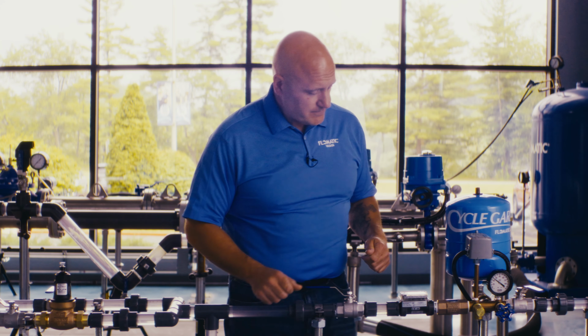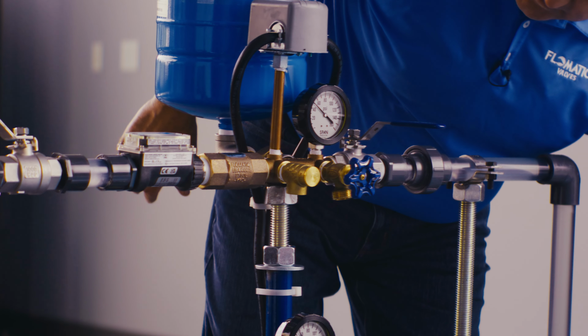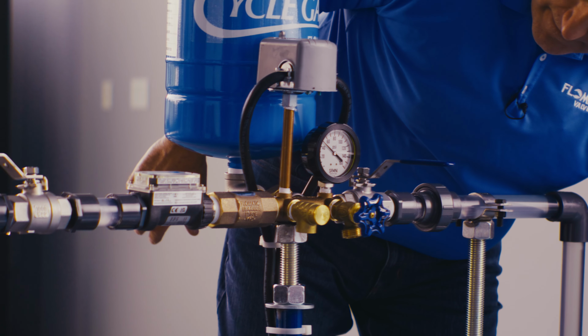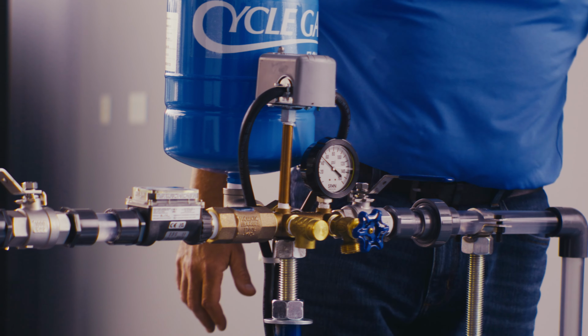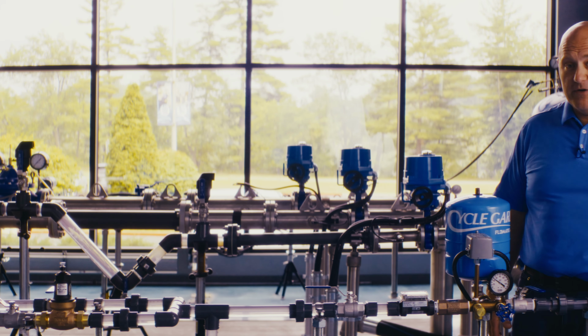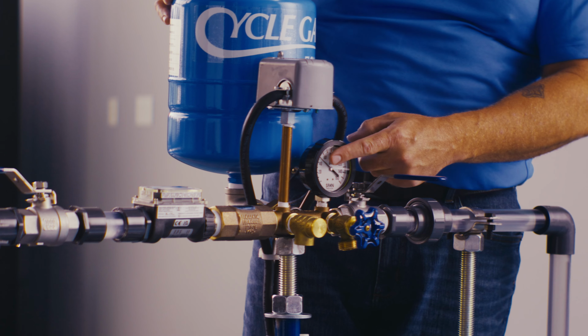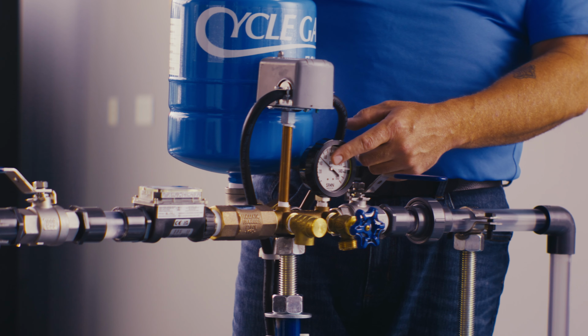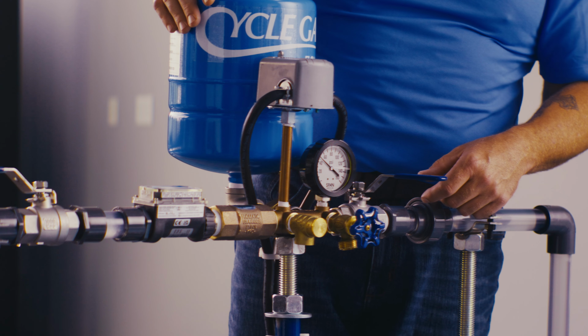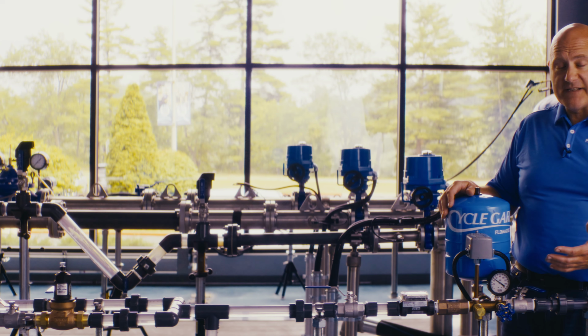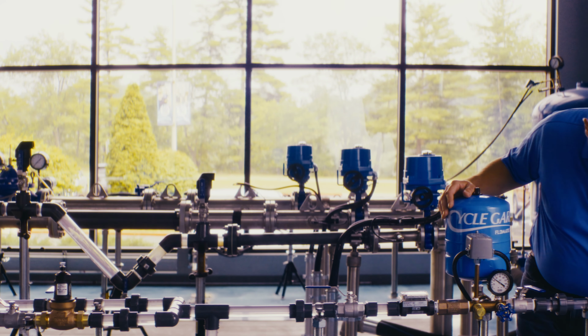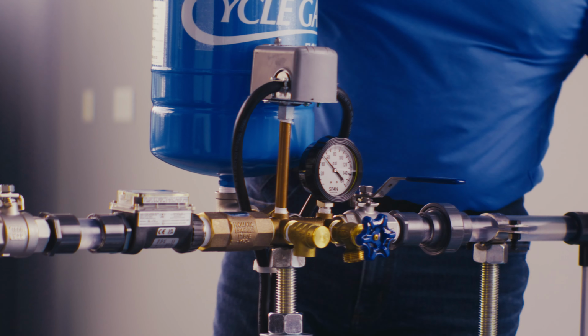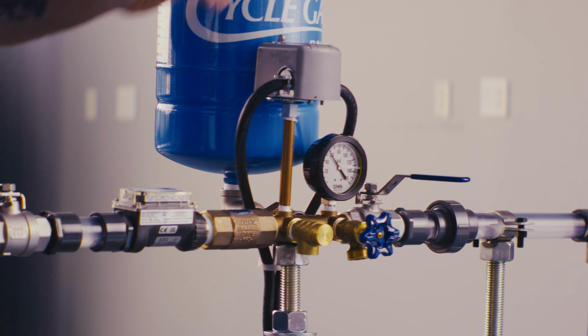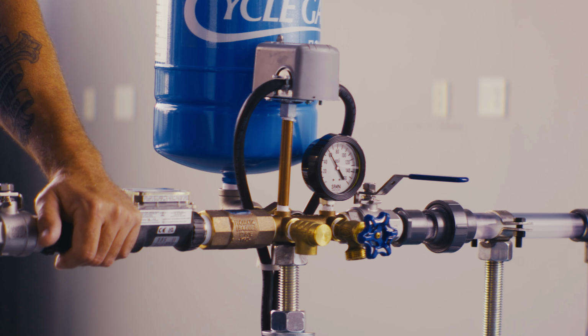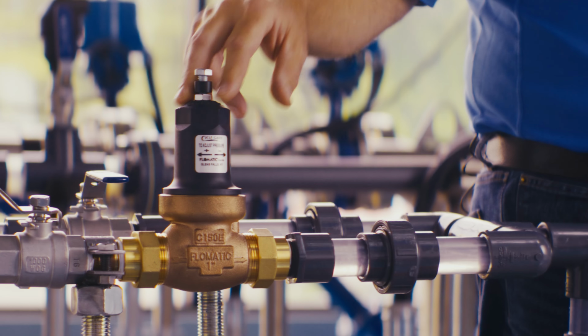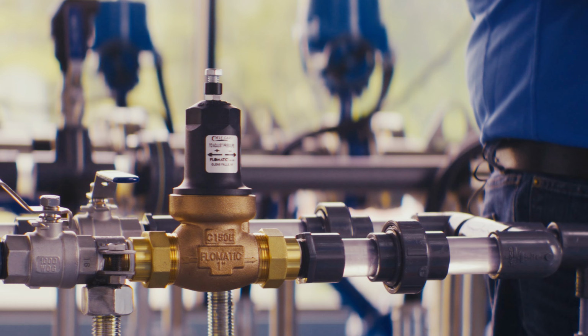to satisfy the demands of the home. So you'll notice if I allow more flow through this valve, meaning maybe a sprinkler system went on or multiple points of use in the home, you'll notice the pressure drops some on our switch. Again, that's a function of the fall off of the valve. Notice the pump's been running nonstop. It has not shut off. It will shut off once and only once the downstream demand stops. We're going to build to 50 PSI, and then the internal bypass on this Cycle Gard will allow the pressure to build up to our 60 PSI and shut the pump off.